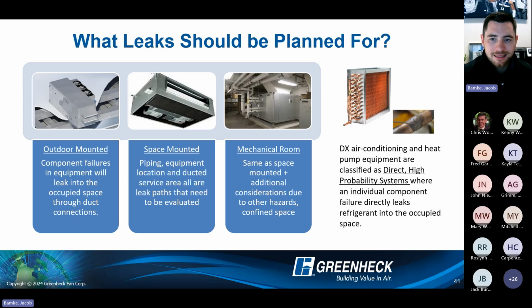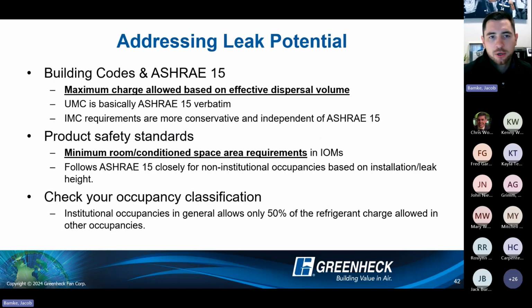systems. And what that means is they're dictated as equipment where an individual component failure directly leaks refrigerant into that occupied space. And it's a high probability that if there's a leak, it will leak into that space. So the question is, okay, we're planning for those leaks. How should we address the leak potential?